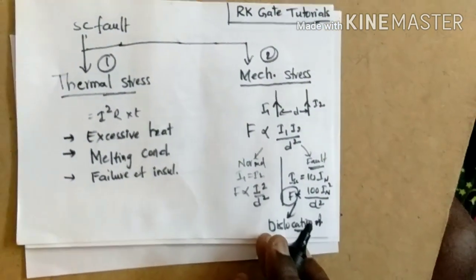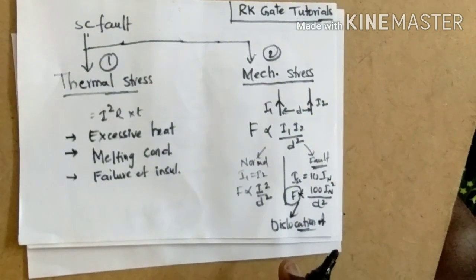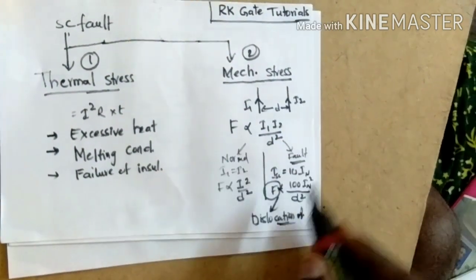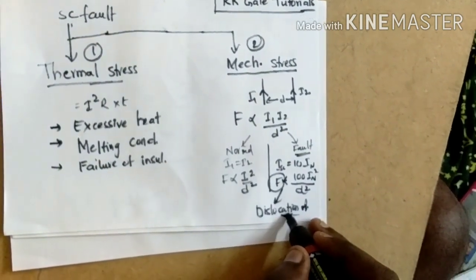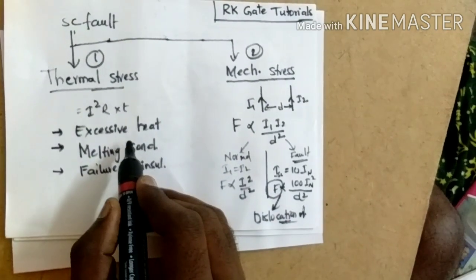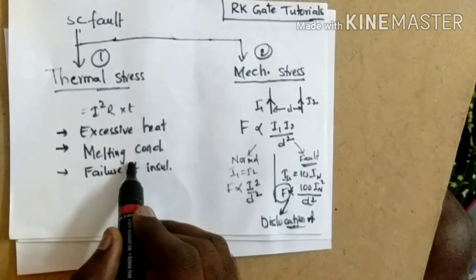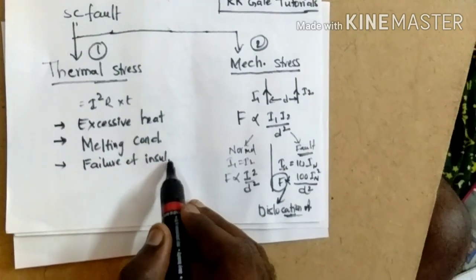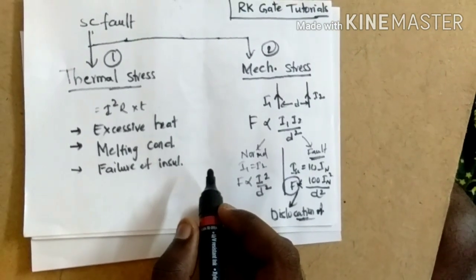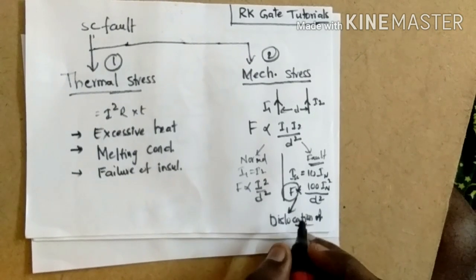Due to this enormous increase in force, there is dislocation of the insulation and conductor. These are the two consequences due to the short circuit fault: thermal stress causes excessive heat, melting of conductor, and failure of insulation; mechanical stress causes dislocation of the conductor and insulation. These are the two important things to remember.